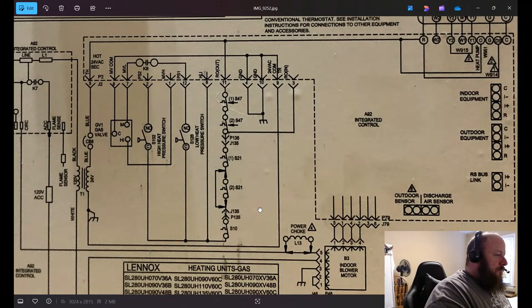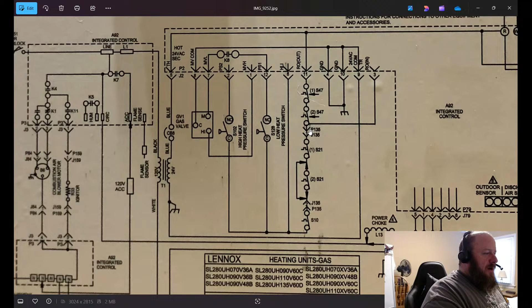Let's move over into our center here. We have pressure switch, 1, 2, 3, 4, 5 temperature switches. So when you're checking out a system, you've got a rollout limit or whatever, you've got to go through all these temperature switches. Counting up how many are in the schematic helps you understand how many you need to check. Okay. Low heat pressure switch, high heat pressure switch.